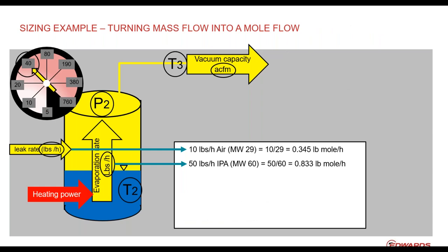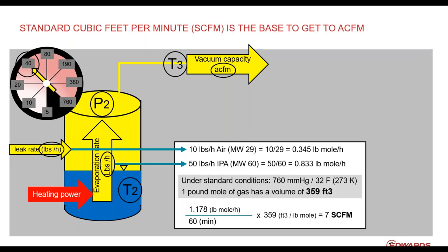Let's go directly to how sizing would work. From the HEI diagram, I assumed a 1,000 cubic foot reactor, landing at 10 pounds per hour of air as the leak rate. I'm also assuming enough heating power to generate an evaporation rate of isopropanol at 40 Torr of 50 pounds per hour. So this reactor delivers mass flow in pounds per hour. All we need to do is apply the mole weights: air has a mole weight of 29, isopropanol has a mole weight of 60. Divide the mass flow by the mole weight to get a mole flow — this is the bridge from mass flow to volume flow.